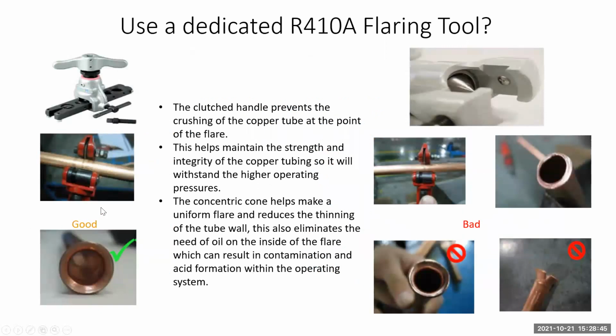Now you want to use a dedicated flaring tool for R410A, because the R410A makes a larger lip on the flaring. You want to be certain you clean everything out, have a good one, nice and smooth. You can move your finger around there and not slice your finger open or something. A couple pictures of bad ones. You obviously want to have a good tubing cutter.